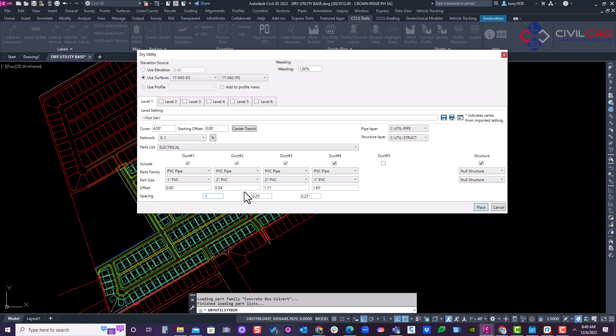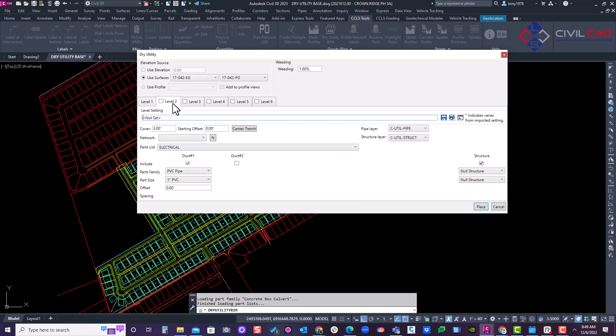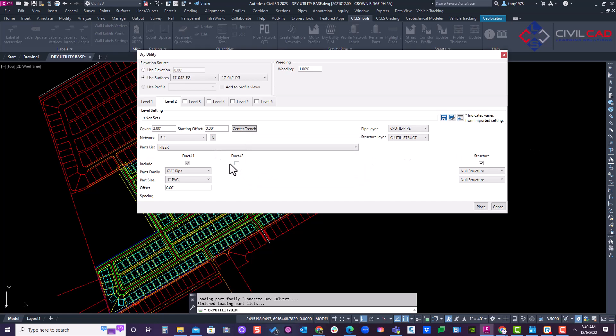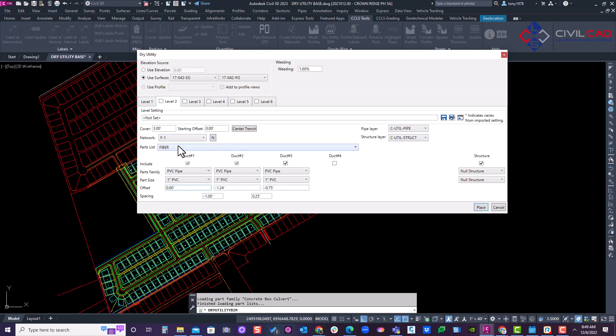Now I'll go to the second layer, set it to three feet deep, and call this fiber. Using pipe networks, I'll name it F-1. I have three fiber conduits, and I'm going to set the offset to negative one for pipe separation. Three feet of cover — hit the check mark.